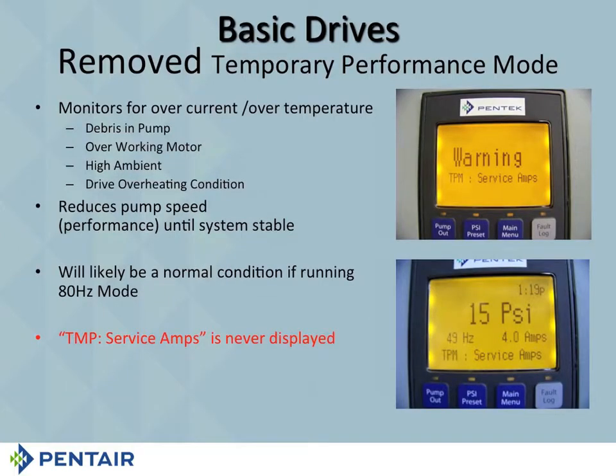We remove the Temp Performance mode as far as what you're going to see on the screen. It is still there, but it's not displayed. What you're going to see now, there's that little yellow warning light down there, and the little yellow warning light will come on when it goes into Temp Performance mode. For those of you that don't know what Temp Performance mode is, it means it's getting hot in here. I've turned the fan on. I've sped it up as fast as I can. I still can't get the heat to go down, so now I'm going to remove the heat another way. And of course, the other way is, let's start slowing the amperage down, because amps are heat. And so it says, let's slow the amperage down so we can bring the heat down. It will run at Temp Performance mode for 3 hours before it trips on over temperature.